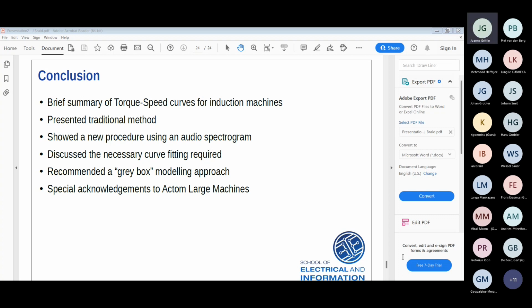Just another comment: controlling the voltage is also not so difficult, to put a voltage controller on it. So you can control it very smoothly so that you don't have to do that much compensation. That's right, and on that note, obviously controlling the voltage for the smaller machines is much easier. When the machine becomes comparable to the generator set, it becomes quite a task, and in fact very often you won't be able to keep that constant, it will drop, you'll have to measure.